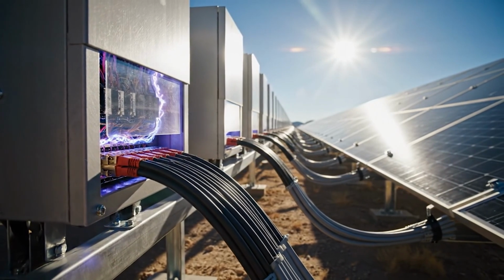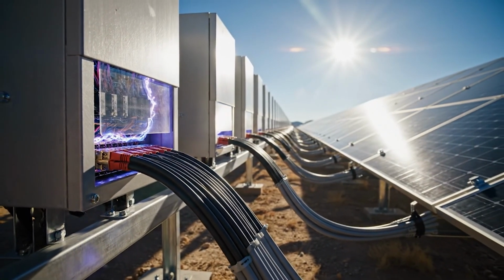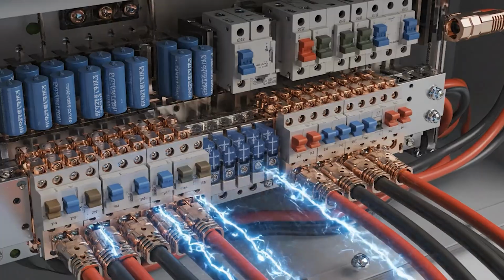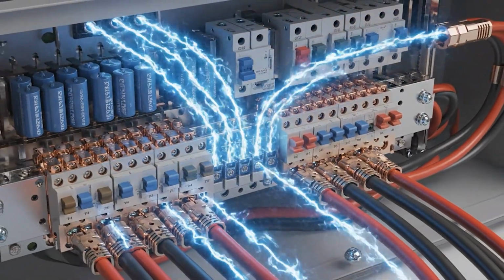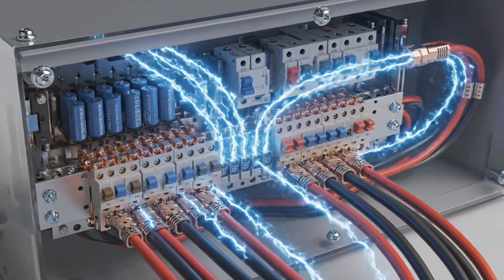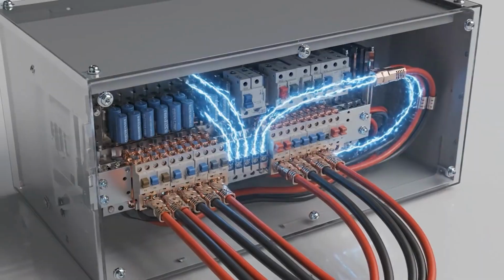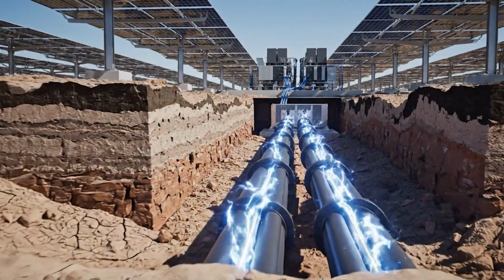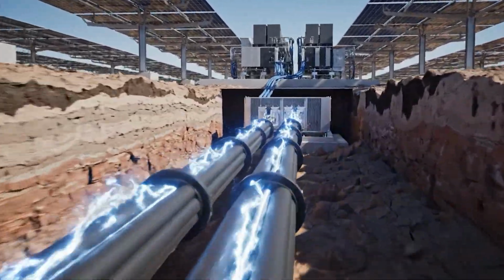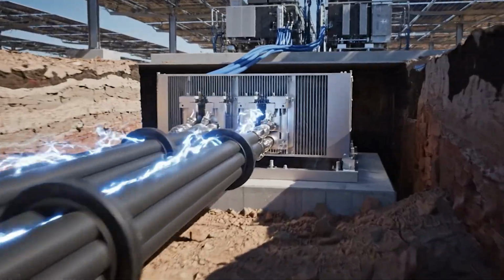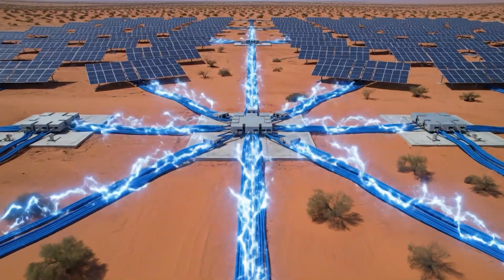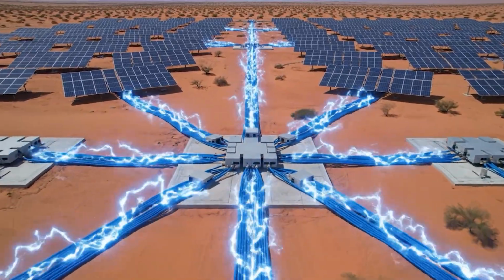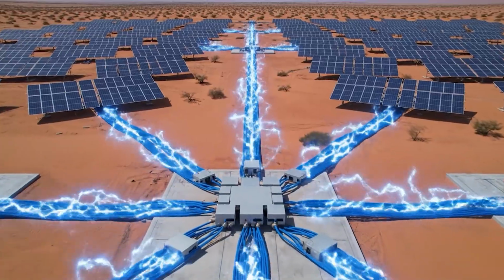Those strings feed into combiner boxes, where many DC circuits are gathered and protected. Inside the combiner, fuses, breakers, and terminals organize thousands of small electrical paths. From there, heavy DC cables carry energy underground towards centralized inverter stations. Across a 10-gigawatt site, this underground cable network becomes a hidden electrical highway.